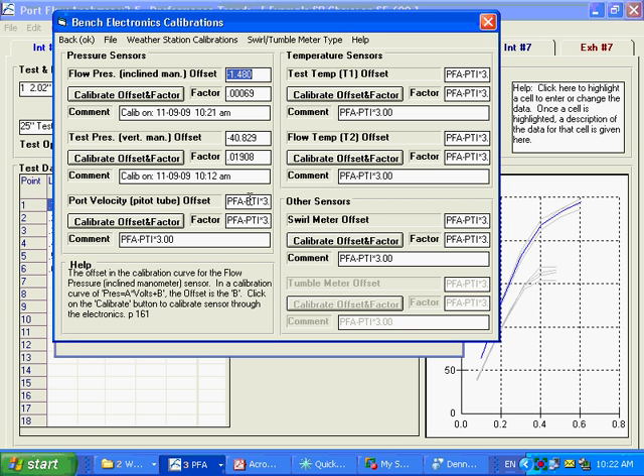Same is true with the pitot tube. Actually here, if you don't have a manometer hooked up to it, the factory calibration is going to be fine for that. Same is true for these test temperatures. I've had people try and set two known temperature conditions by boiling water. The problem is the range of these temperature sensors don't go up that high. So it's pretty hard to set two known temperatures other than the dial gauges on your 110, trying to match them.